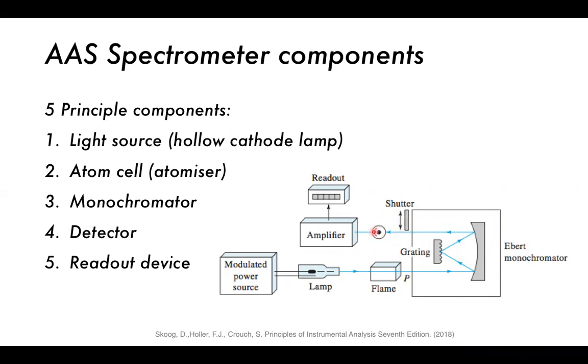We also have a modulating device like a shutter or chopper, which can chop the light to produce it in packets. Then we have an amplifier to amplify the signal, and a readout device — could be a computer or simply a screen. So the five principal components are: the light source (typically a hollow cathode lamp), the atom cell or atomizer, the monochromator, a detector, and a readout.